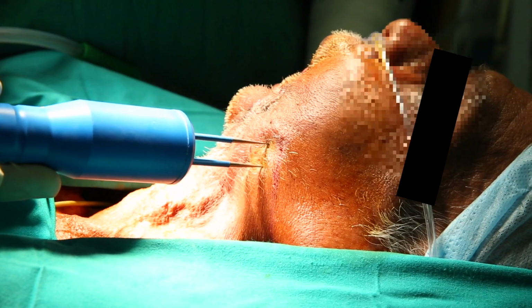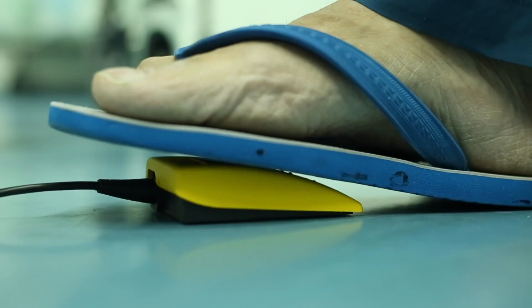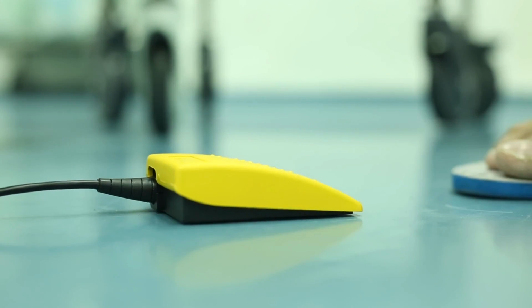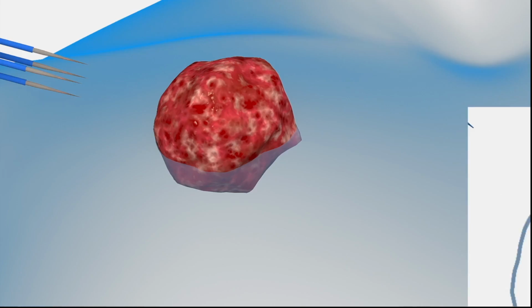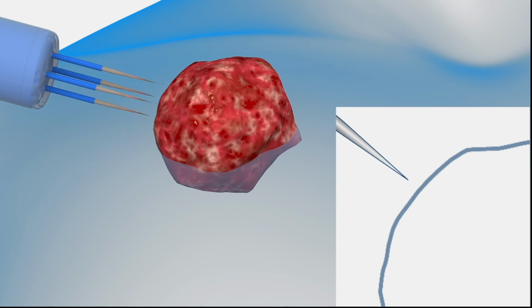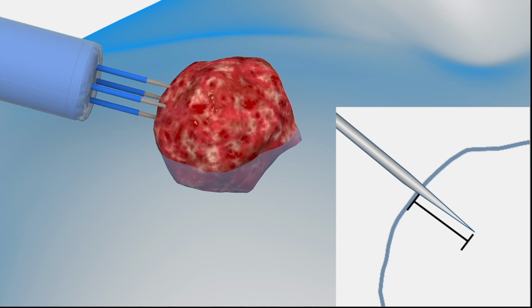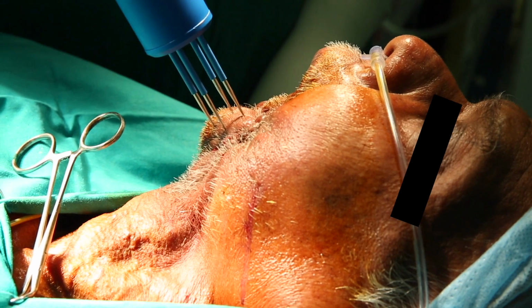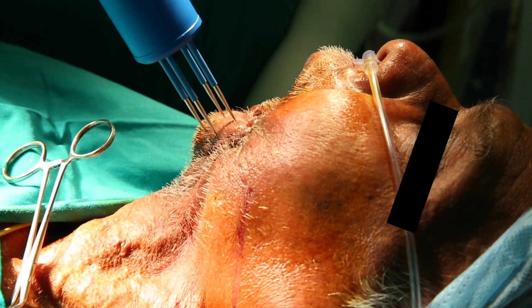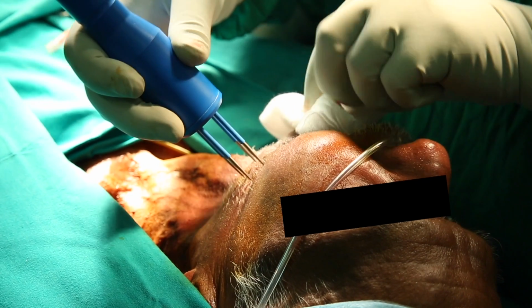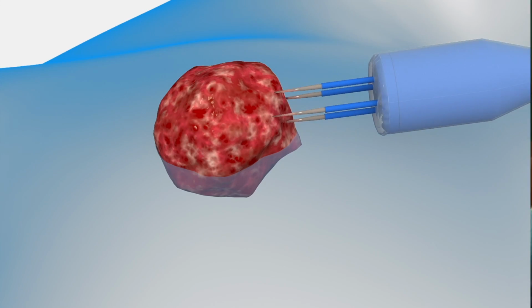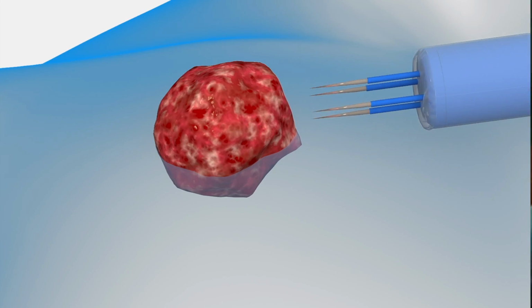Electrodes are positioned 5 mm away from the tumor area. The technician presses the foot pedal of the device to release electric impulses. The needle electrodes penetrate to a depth of 15 to 20 mm to deliver impulses to the tumor. The doctor works his way from the periphery to the center of the tumor. 8 impulses are released in every insertion. Several insertions may be required to cover the entire tumor.